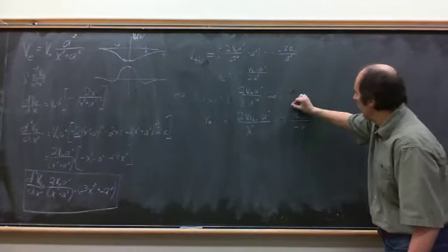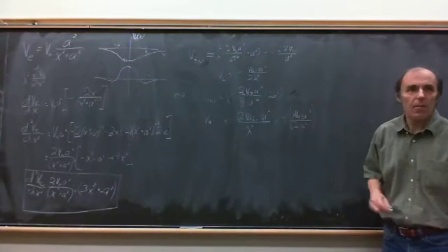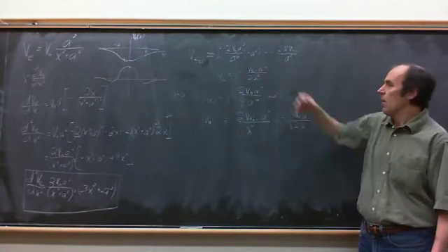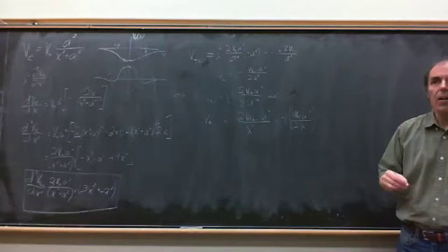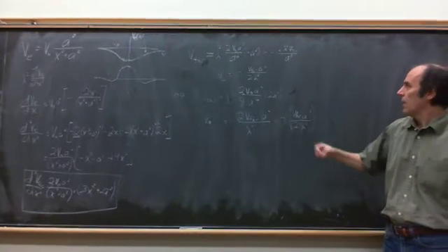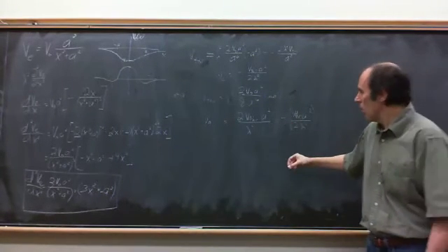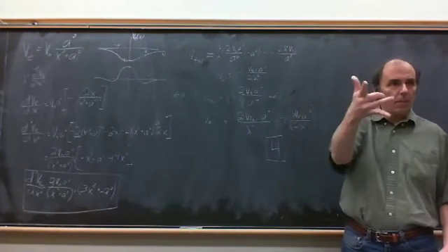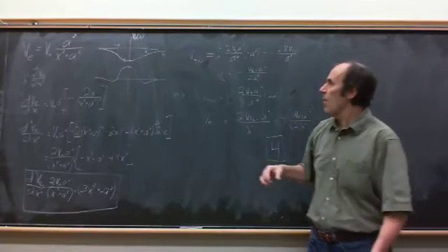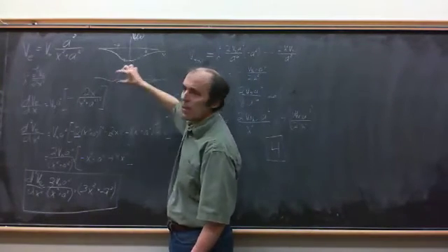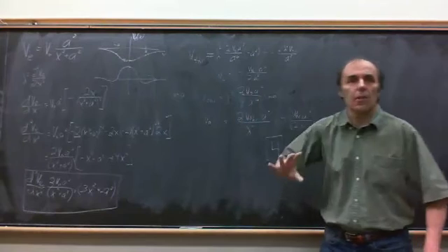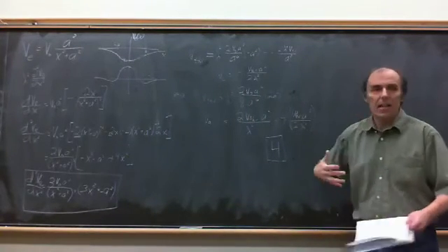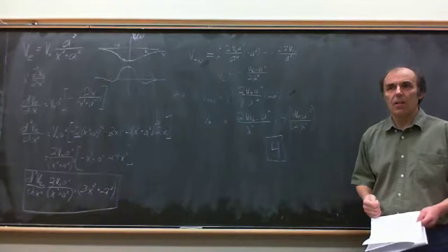Now why do I do that? Why did I do it with the 4 out front? Because this is exactly the same as that. So if I want the ratio of anode to cathode, it's just going to be 4. So really the answer is 4. If I turn the stimulus to opposite polarity, so now I've got to stimulate on this little peak instead of the big peak, I've got to turn the stimulus knob up by a factor of 4. And that's the idea for the calculation.